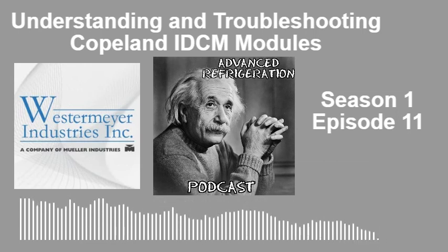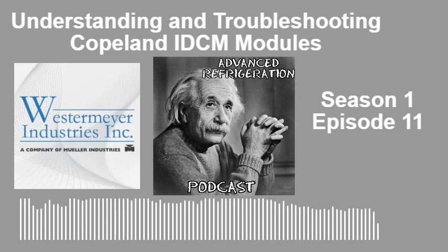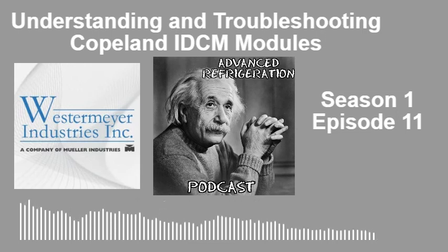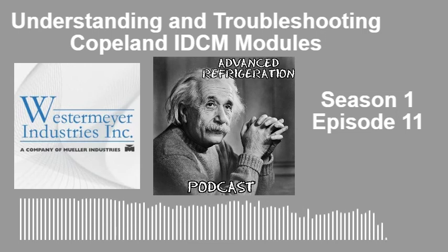Basically, with a regular standard unloader, let's just say, for instance, you have a 4D. That 4D might be 20 horsepower, and then when you unload half the heads, now it's a 2D. So you can unload it off and on like that. With the IDCM, you don't have to go from 100 to 50, 100 to 50. You could actually load that compressor from 50 all the way up to 100 in increments using the cycling on that solenoid.